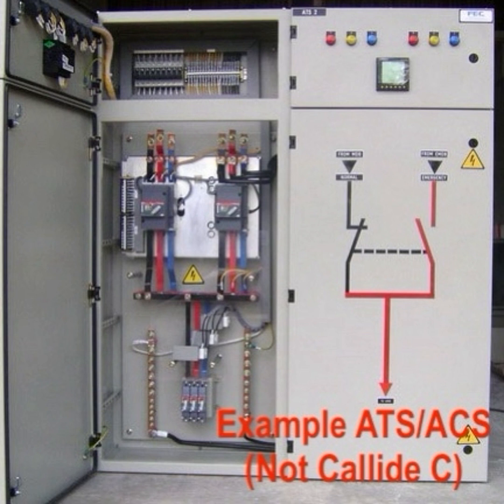To ensure the preference is for the unit DC battery charger to supply the bus, it should have been set to a slightly higher voltage than the station charger. However, the station charger's output was set higher. Based on the information in the reports available, it's unclear why this was set in this manner. However, in the press conference Q&A, it was stated that this was set during the original design.